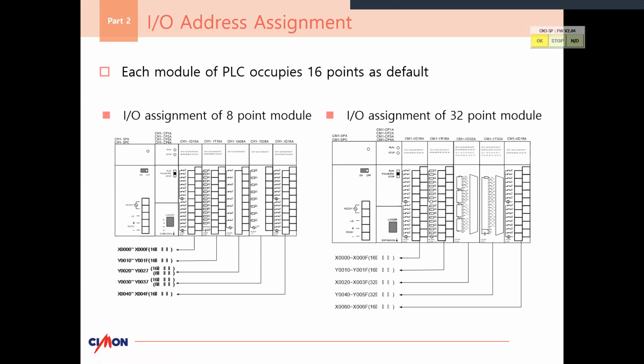As you step up to a 32-point module, referring to our digital inputs and outputs, every other module besides digital input and output will be allocated only 1 word each. When we step up to 32 bits, we get 2 words of each, because we have 32 bits, so we need 2 words to allocate for that. The same goes for a 64-bit module, which needs 4 words, because that's 4 words of 16 bits. I'll showcase that on the Cimon simulator.